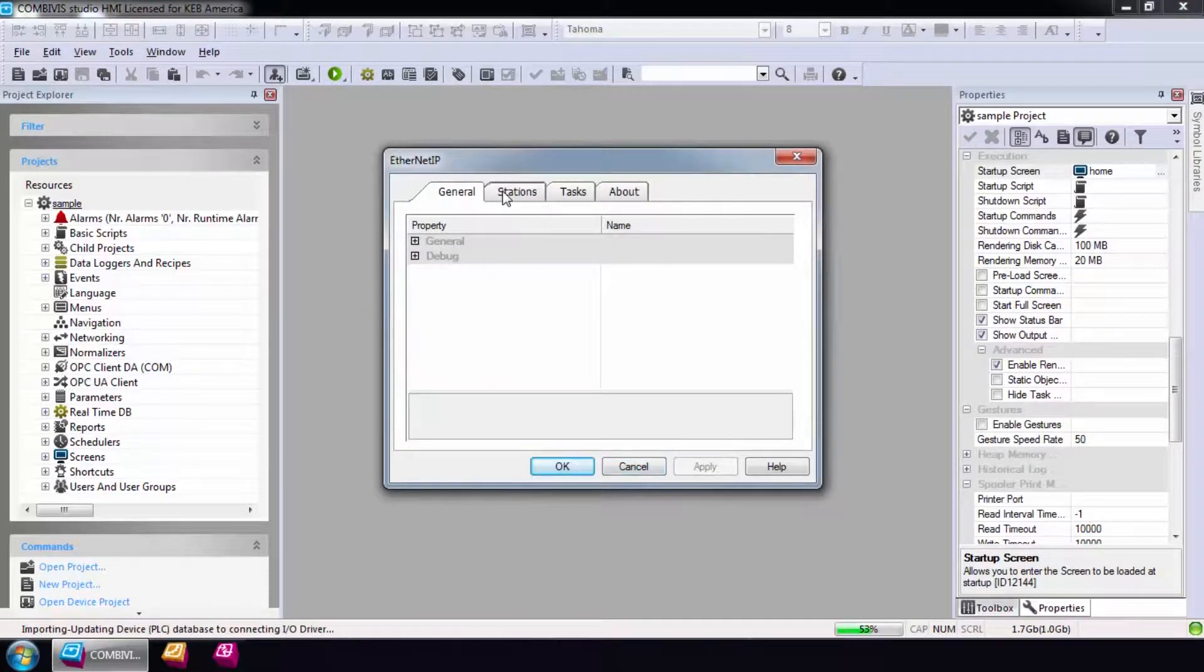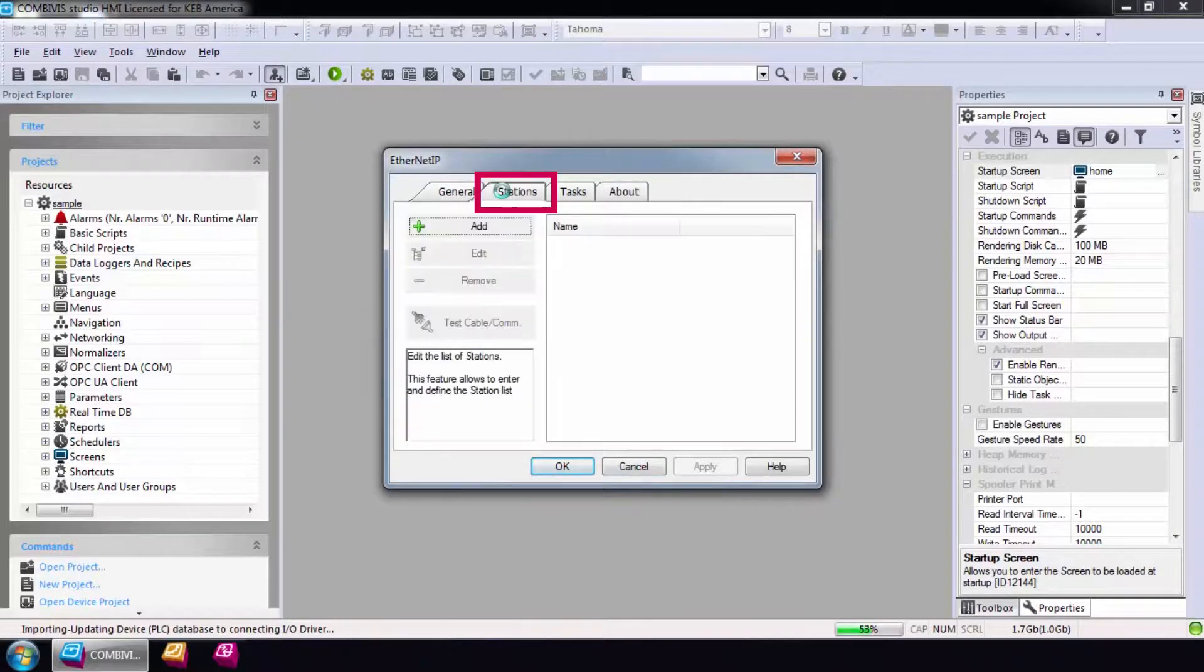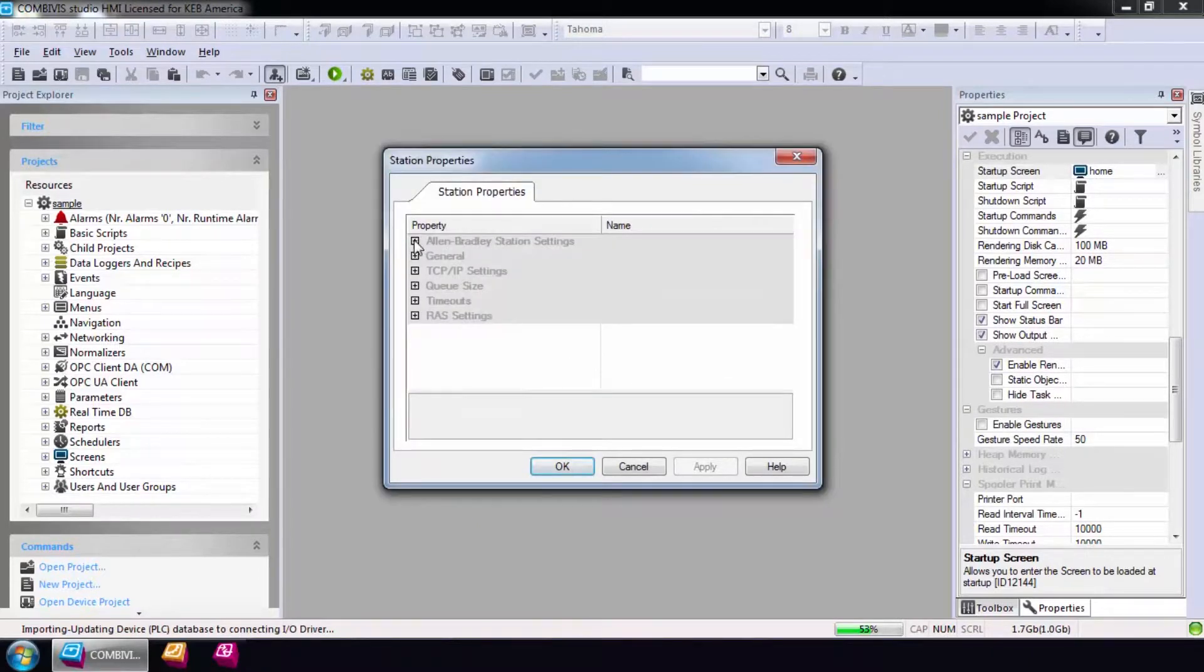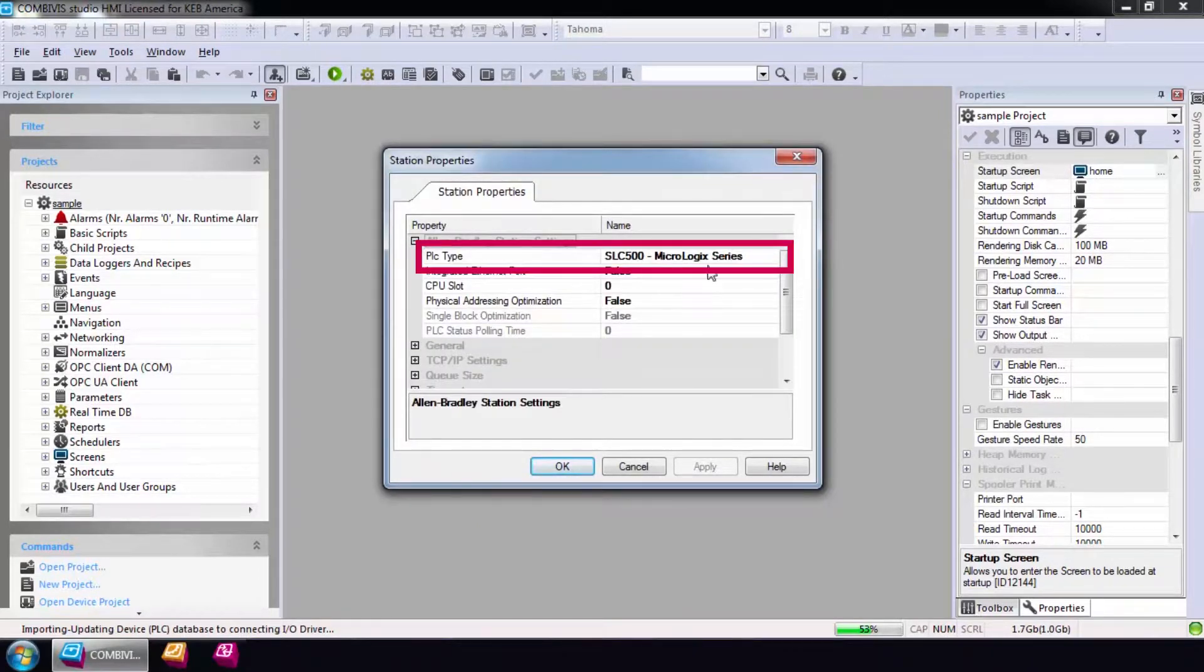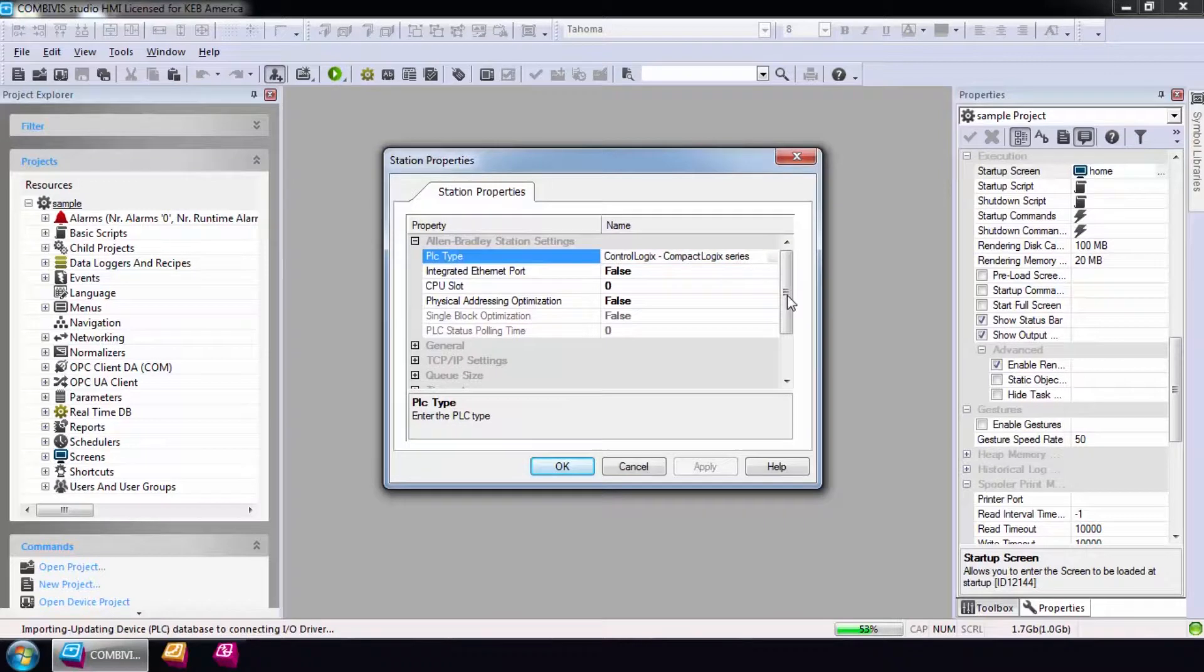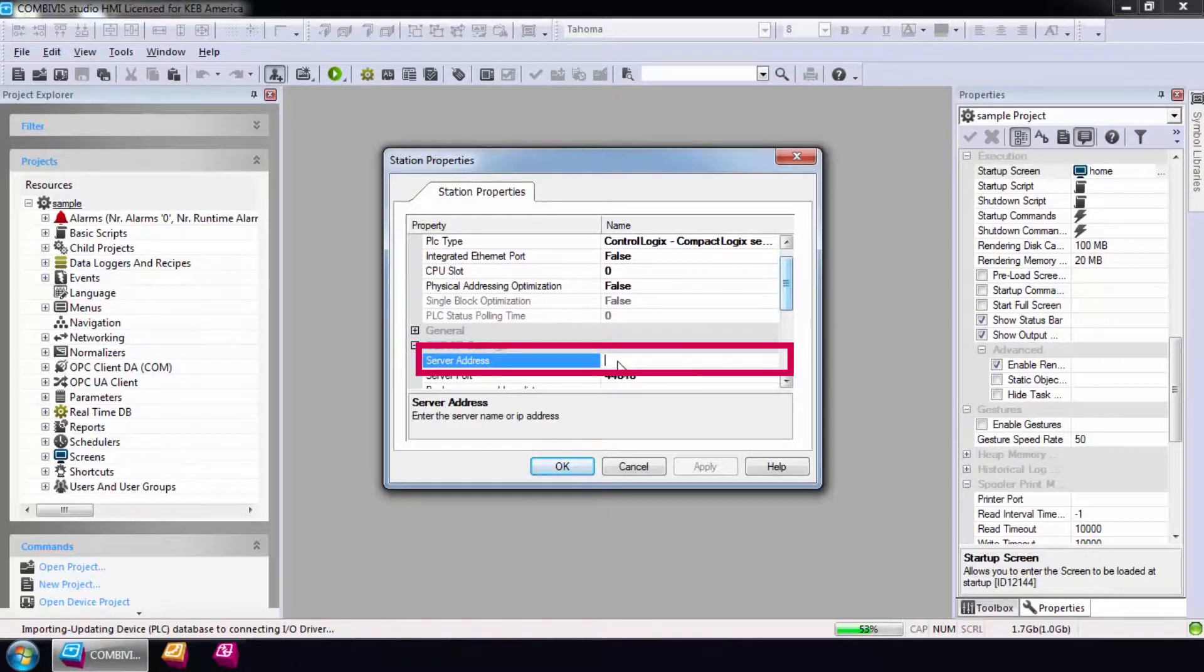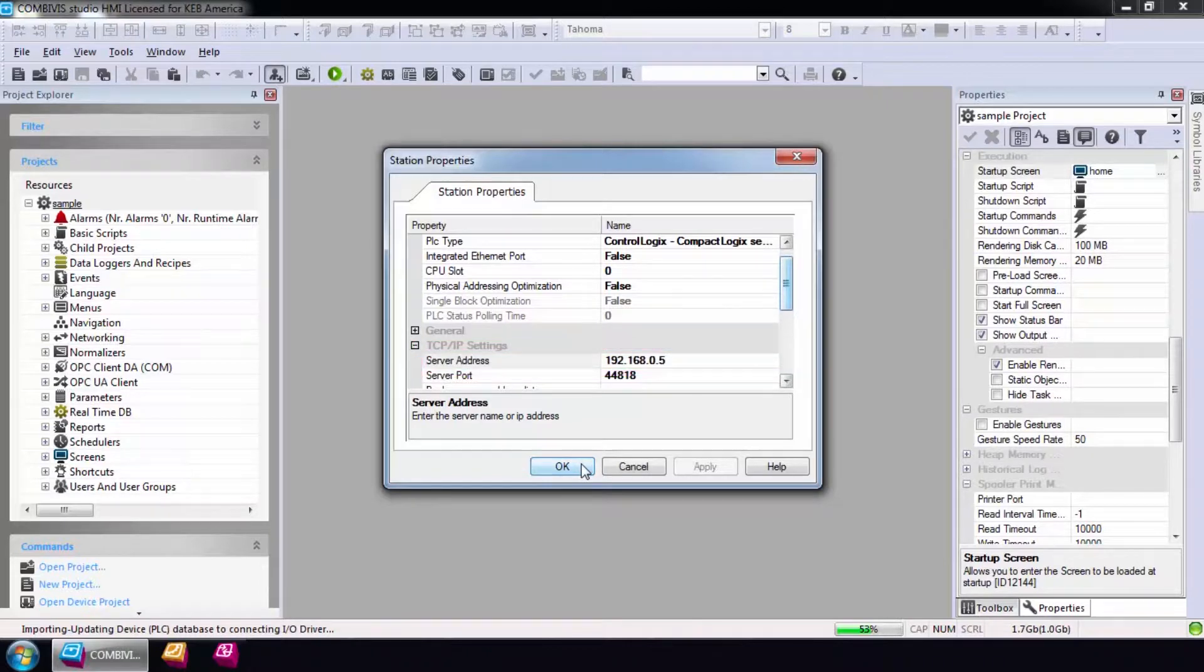The first pop-up you will see is the Ethernet IP configuration wizard. The only thing that needs to be configured here is a station with the correct IP address of the CompactLogix. Select Station and Add and modify the PLC type to CompactLogix, then scroll down and enter the IP address of the PLC.